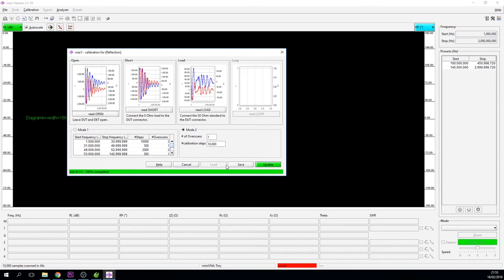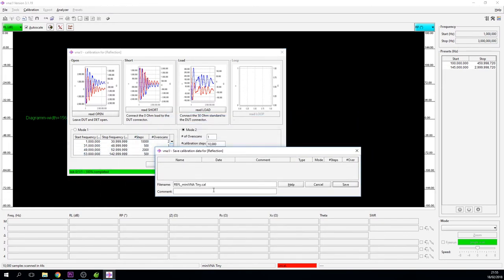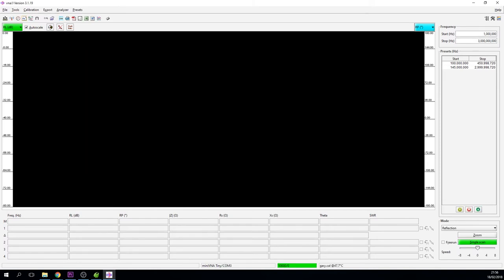So now the save is actually illuminated and I'm just going to say save and it's now asking me what I want to call it. I'm going to call this Gary Cowell and you just say save. Now at this point we can then say update and the box goes away and that pretty much is it done. It's telling us what we're using down here as our calibration, it's giving us the temperature of the unit and pretty much that's done.